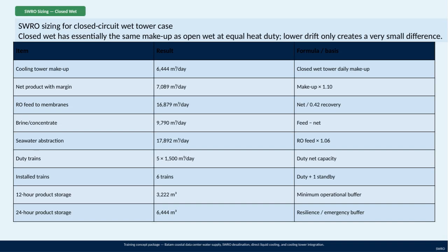Here, we're looking at the SWRO sizing for a closed-circuit wet cooling tower setup. The key takeaway is that the closed wet system is very similar to an open wet system when operating at the same heat duty. The only difference is a slightly lower drift, which doesn't significantly impact the overall makeup water requirements. Focusing on the table, we see that the cooling tower makeup water volume is 6,444 cubic meters per day, which is a baseline for the closed wet tower.